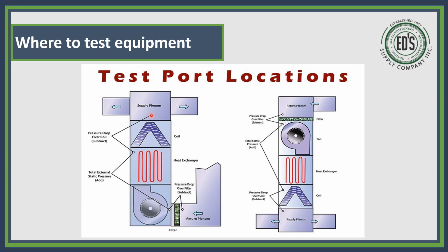So I like to test mine here and right here. The reason I'm testing it here is because this area right here is the exact resistance that the blower motor is going through. I want to make sure of that because it's going to go over this coil. So here is the external, and this is the external here, of what that unit is actually going to deal with. So I'll put a probe here, and I'll put a probe here.